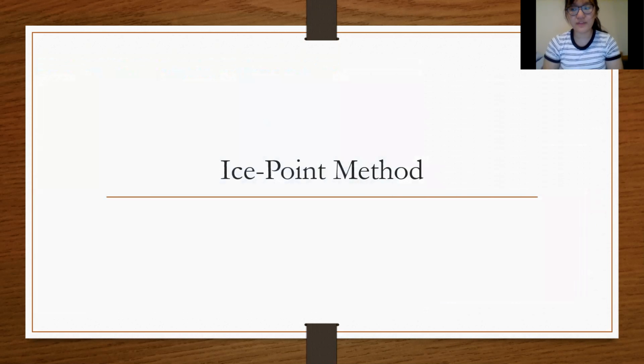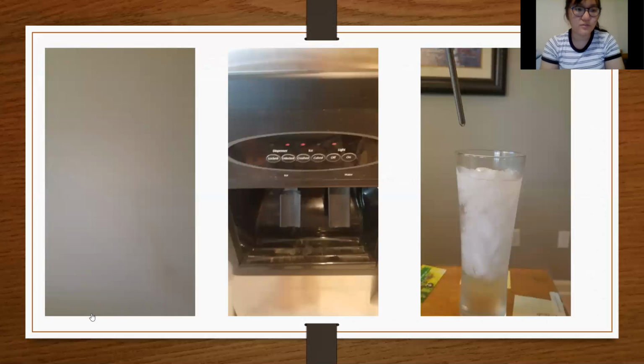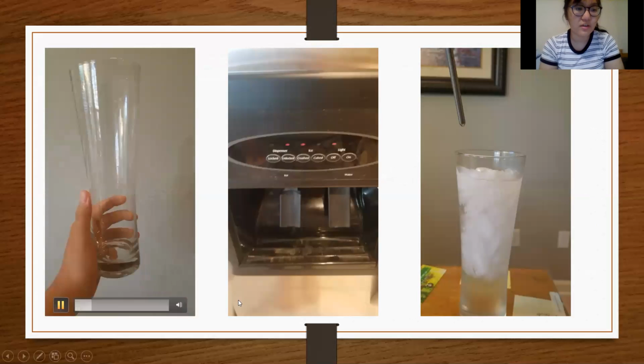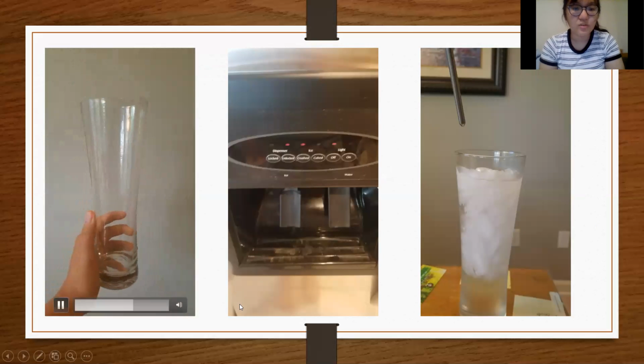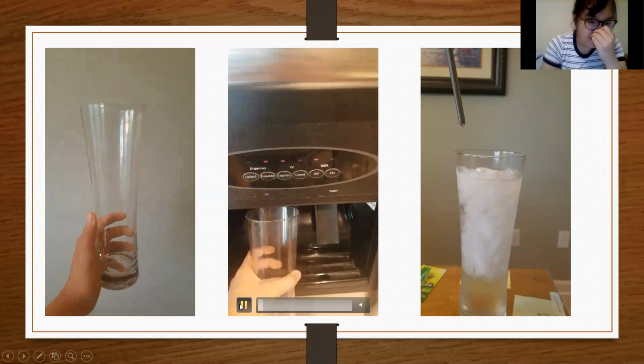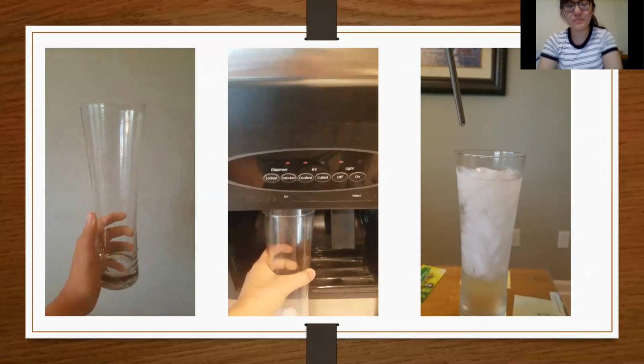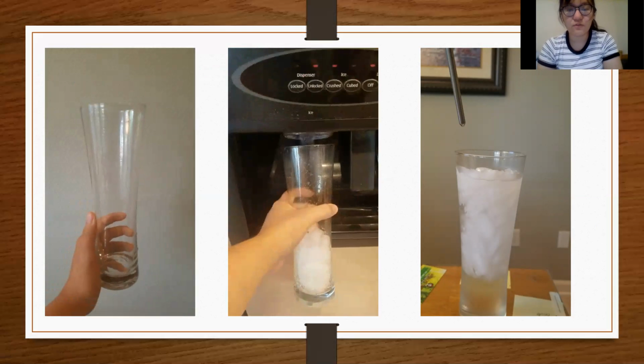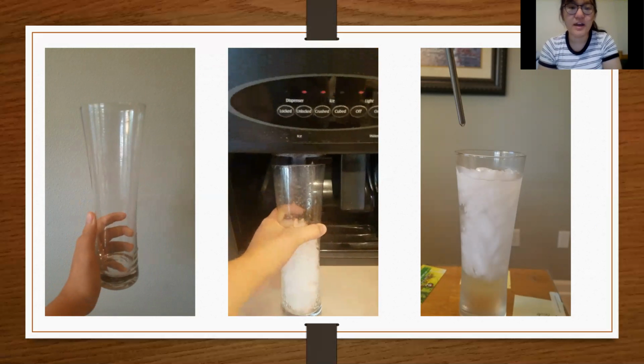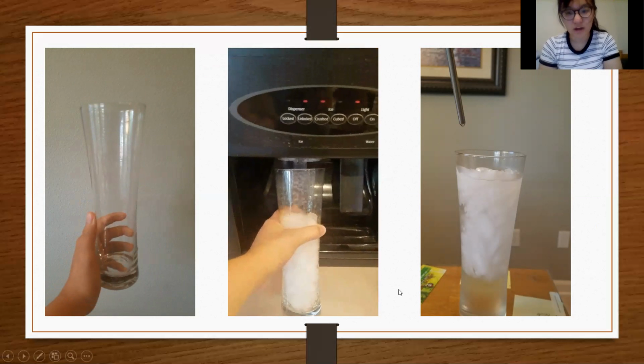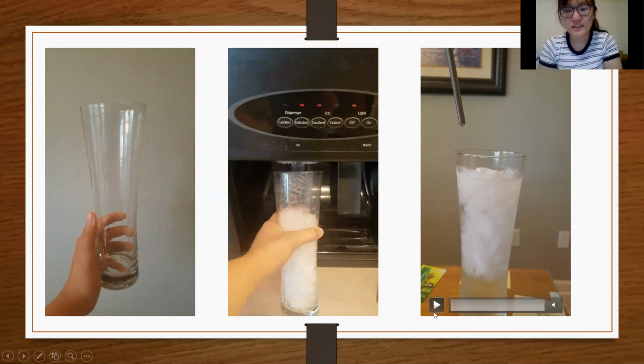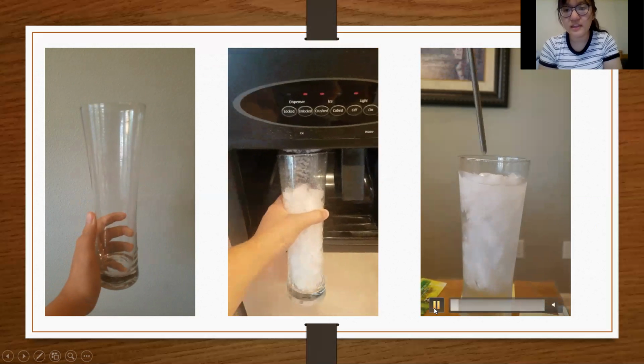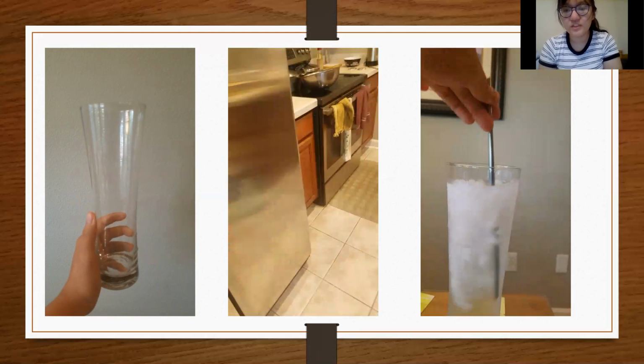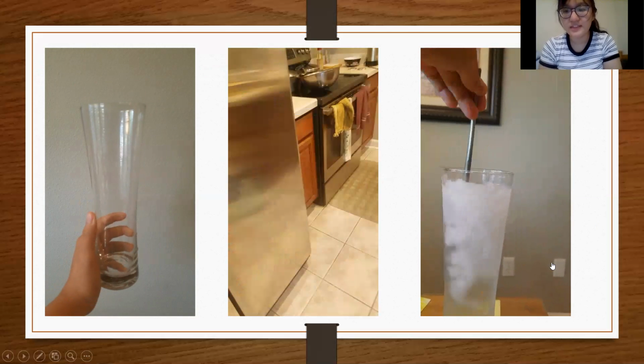The first method of calibration that we have is the ice point method. So what you do is you find a container that is tall enough to fit your thermometer in, and what you want to do is fill that container with crushed ice. And you use crushed ice because it's easier for the temperatures to even out as you fill it with tap water. And after your container is filled, you'll want to give that a quick stir just to make sure that the temperature is even.